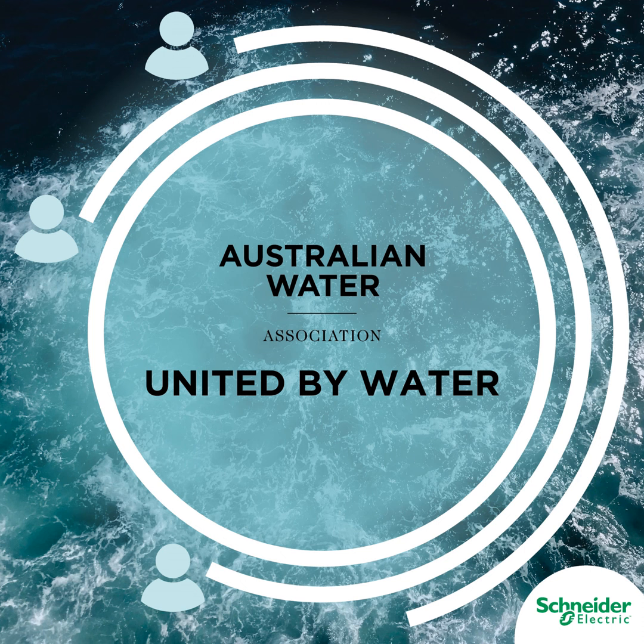Tell us what was going on at one of your water treatment plants. Sure. So at our Winneke treatment plant, which is one of our 3 largest treatment plants in Melbourne, we had been doing our usual yearly inspections of our filters. Winneke is a classic sedimentation media filtration treatment plant. We found that the filters were starting to show signs of poor condition, so mud balling, and also some significant cracking at the backwash inlet end of the filters.